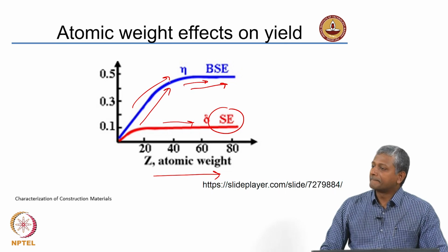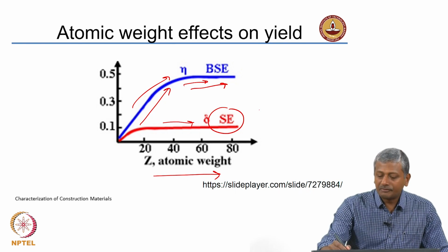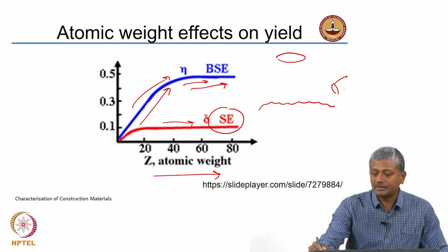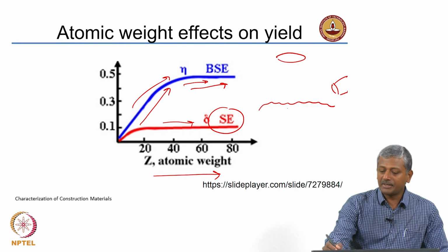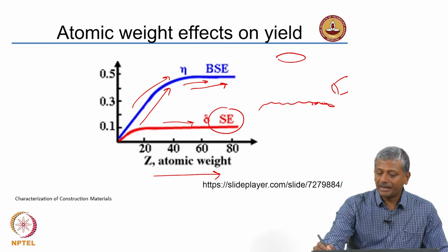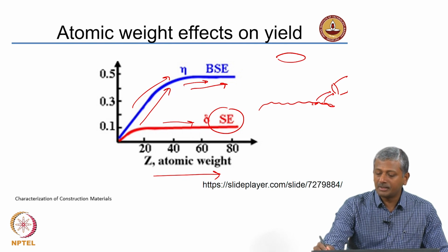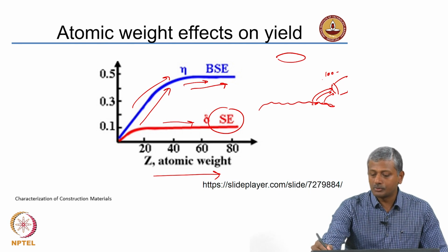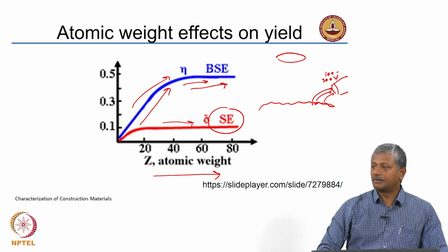Yeah. Will the secondary electrons coming from the, if this is your sample, the backscatter detector is right on top, secondary electron detector is here, right. So, what is happening is the secondary electron yield is only from the surface, and because the electrons are low energy, they are getting captured by the positive potential, that is 100 to 300 volts that you apply in the Faraday cage, right.